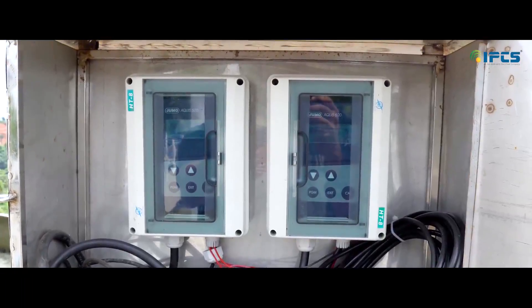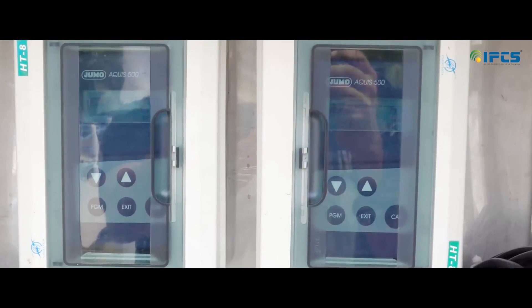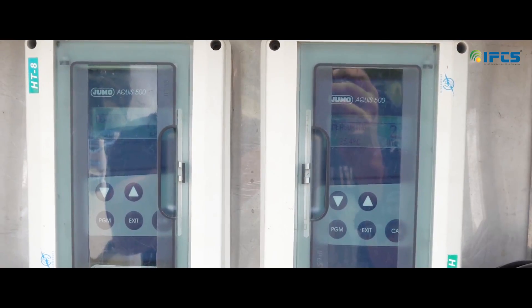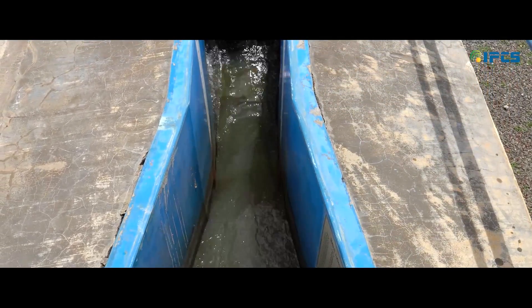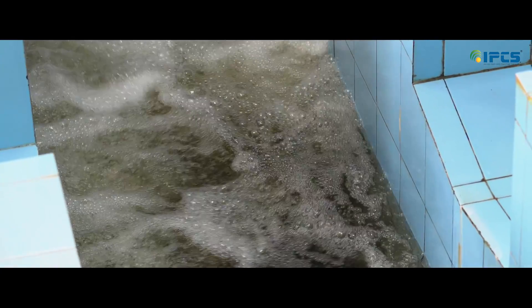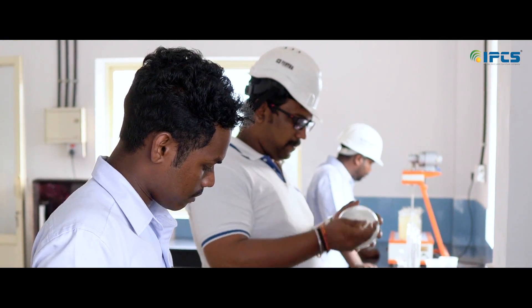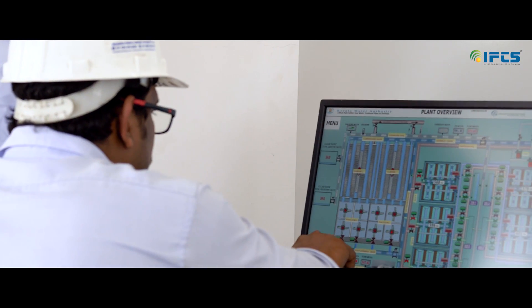Right after the aeration section, the water is fed into a channel where the flow rate is measured. Here we are using a Parshall flume and ultrasonic level transmitter to measure the flow rate. There is also a scale on the flume for manual measurement. From the same channel, water samples are taken for determining the pH and turbidity rate of the inlet water. The transmitters have local display and also data communication with SCADA.